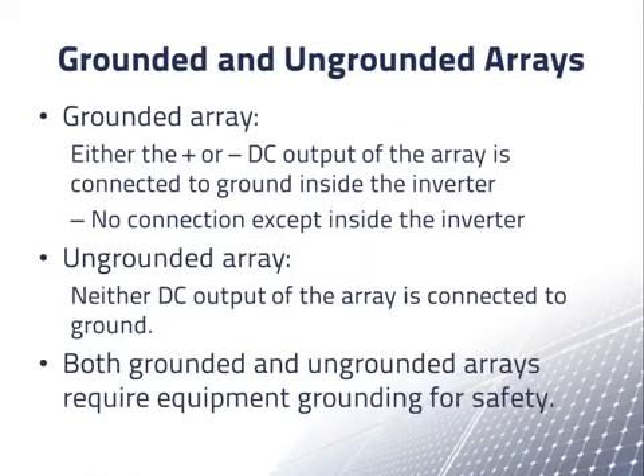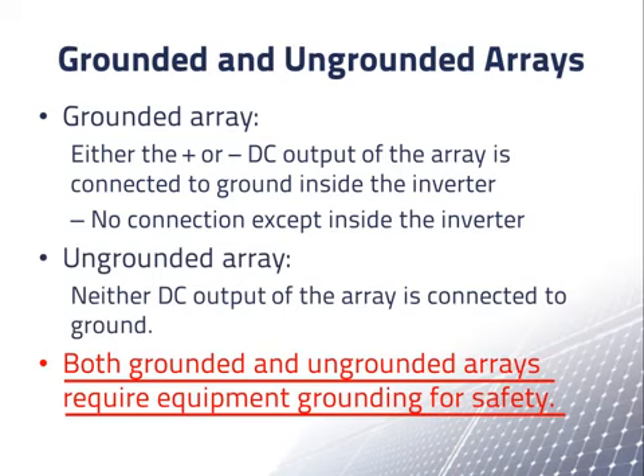We have previously discussed grounded and ungrounded arrays. Recall that a grounded array is an array in which either the positive or the negative DC output of the array is connected to ground inside the inverter. Neither output is connected to ground anywhere else. An ungrounded array is an array in which neither the positive nor the negative DC output is connected to ground anywhere. Both grounded and ungrounded arrays require equipment grounding for safety. What we are going to discuss here applies to both grounded and ungrounded arrays.